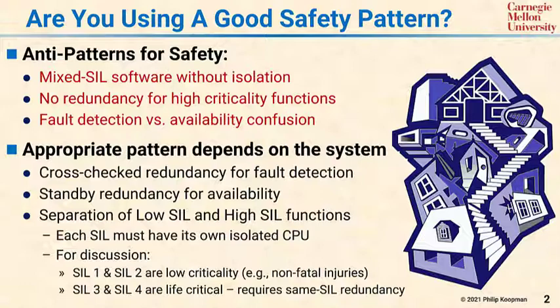So when we talk about low SIL, we mean SIL 1 and 2 — nobody dies. When we talk about high SIL, we mean SIL 3 and 4, which are unacceptable consequences and therefore require extra redundancy. High SIL systems have to be safer than typical hardware reliability, so you need redundant components to make sure that in the likely case where one component breaks, there'll be another redundant component to provide safety.